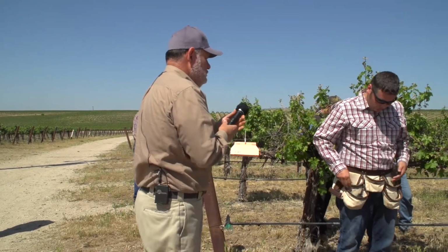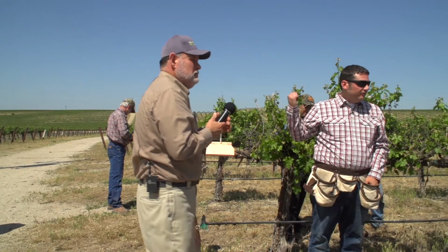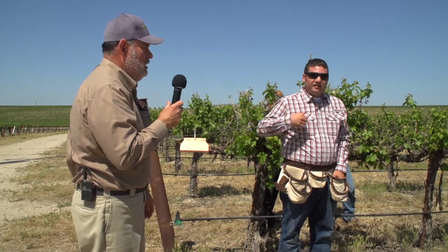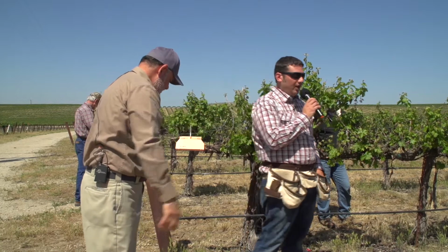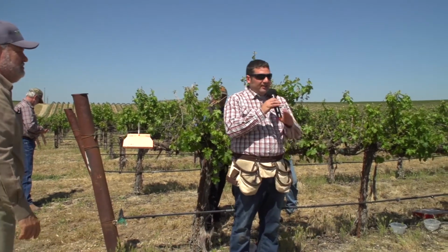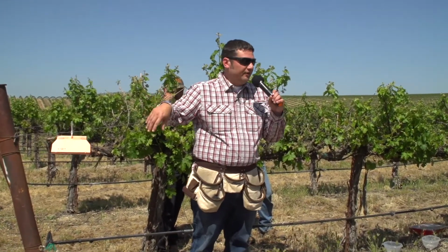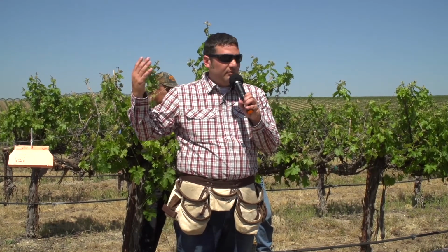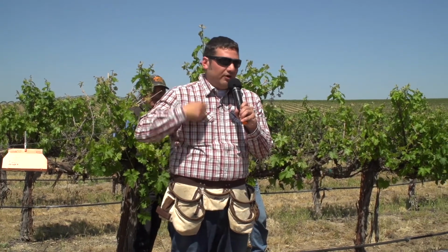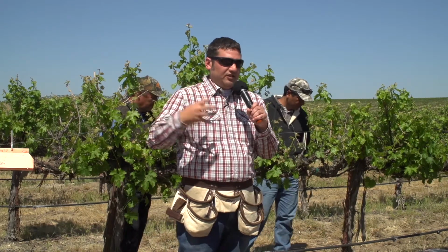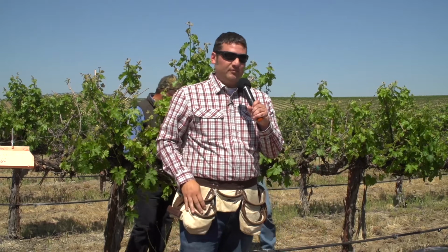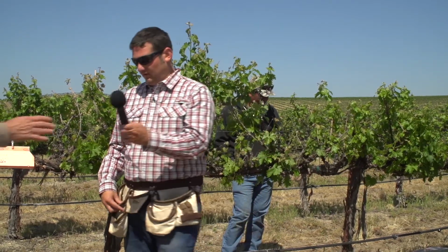And so while we're letting this run, we're just going to go ahead and do a flush out at this last line here. That's another important thing that we do. When we flush, we're not just going to let that little shoot out until the water runs clean after a couple seconds. It's letting that water run for a long time at a high pressure so that turbulence and velocity break up any of that precipitate, scale, and all that stuff gets loose and actually out of the system. So it's not a couple second flush, it's a 10-minute flush.